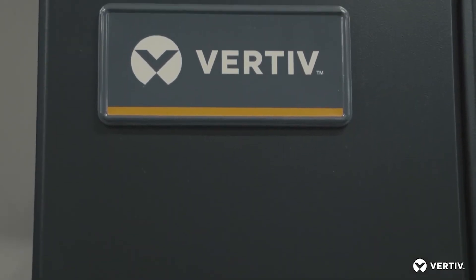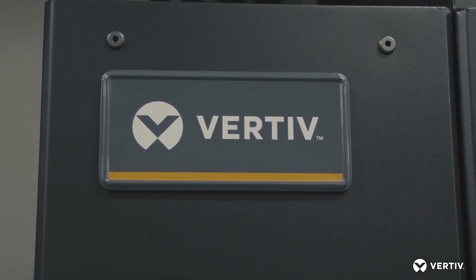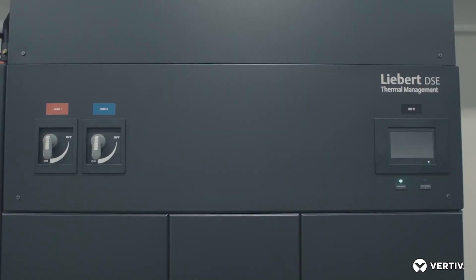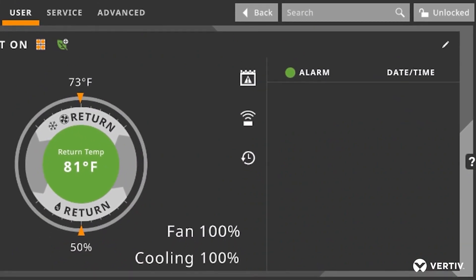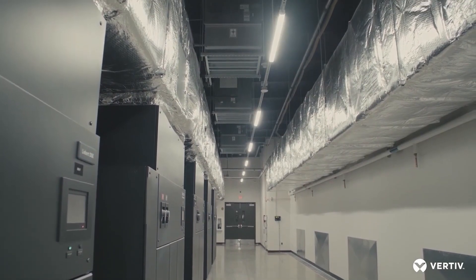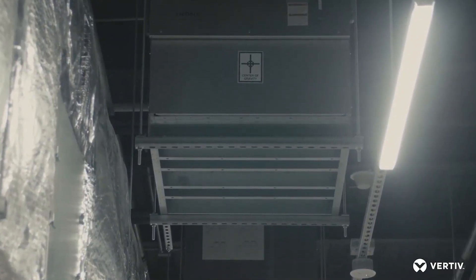We use Liebert's DSE Free Cooling System, which includes econophase pump refrigerant economization in the Akron Data Center. The technology offered by Vertiv and their DSE units has been able to leverage higher outside temperatures to continue econophase versus water-based cooling, where we would need colder outside temperatures to achieve efficiencies.